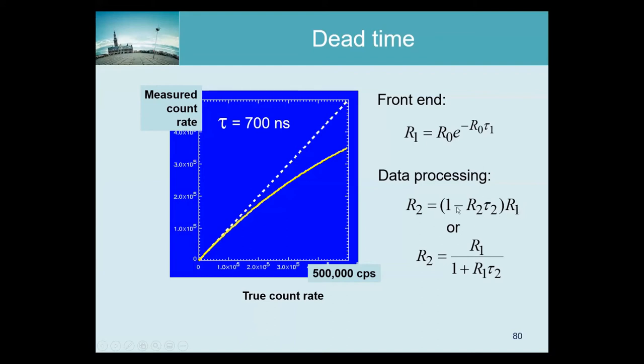Computing r₂ from this expression shows that if r₁ is small compared to 1/τ₂ the system is always ready and r₂ equals r₁. If r₁ is very large, r₂ approaches 1/τ₂ — the maximum count rate. If the system can process 100,000 photons per second and you give it a million, it will process 100,000 and discard 900,000. This behavior is called non-paralyzable — the system does the best it can and saturates at a maximum.